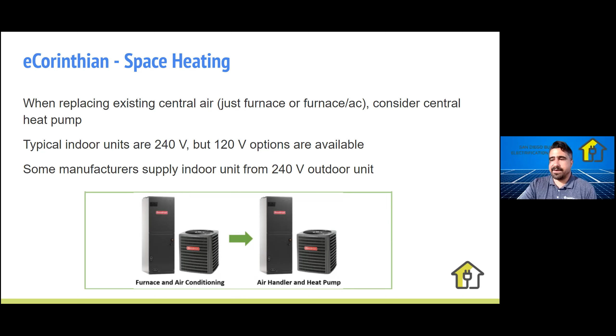Typically the outdoor units are 240 volts, whether doing heating or just air conditioning. The indoor units also tend to be 240 volts, even though furnace indoor air blowers tend to be 120. But there are options to reduce electrical demands or changes — there are 120 volt blowers, and some manufacturers supply power to the indoor unit from the outdoor unit, which can help reduce costs.